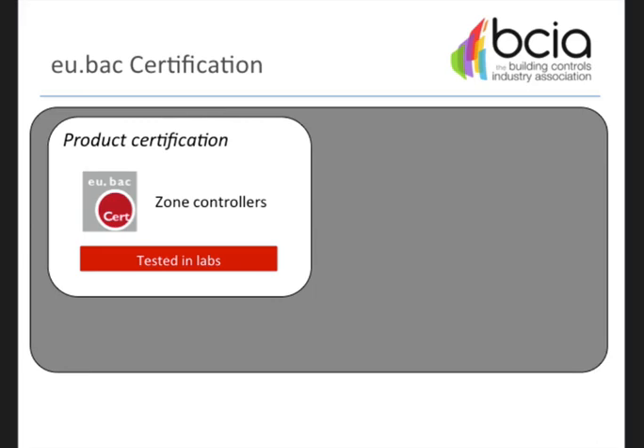I had a big problem with this because it meant you had to deliver your controller pre-configured and engineered to this standard. They would test it in a lab and send it back to you. That's great for a fan coil controller, a boiler controller, or a fixed application controller. The gap I saw was the configurable controller and the quality of the configuration by the configuring engineer.